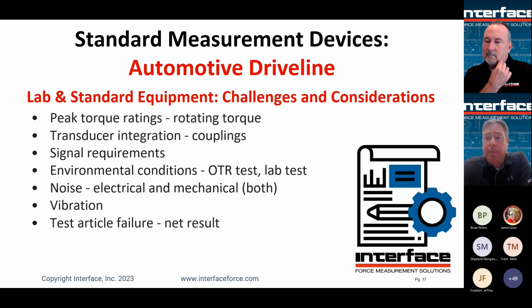Noise. Rotary torque typically seems to be more susceptible to noise effects. You've got perhaps electrical noise being transmitted from VFDs and different drives on the actual rotating shafts, and isolating the transducer from those can be very challenging. So making sure you've got a good grounding scheme put together and implemented is absolutely key. And then, of course, there's always mechanical noise in these test stands potentially as well. So how do you isolate? Is it electrical? Is it mechanical? Getting good grounding to get the best results is always key.